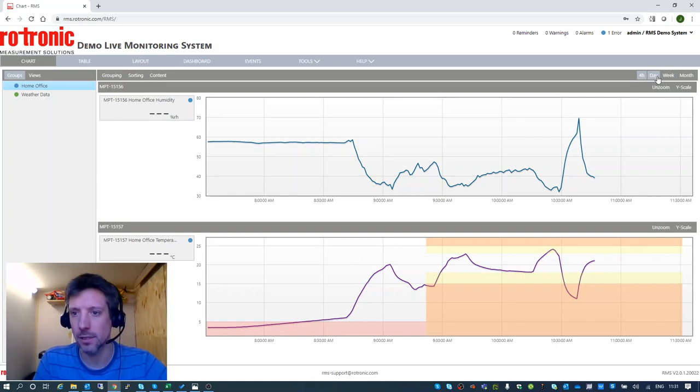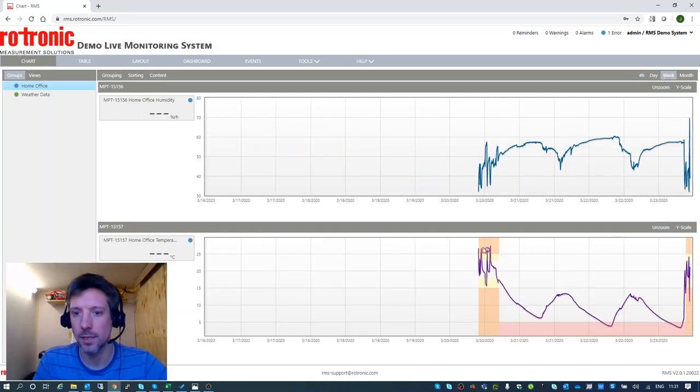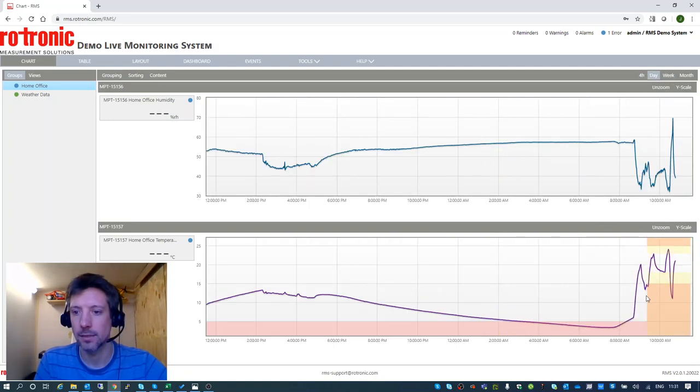But we can see that over the weekend we had, this was Friday's monitored data, and we can see the alarms adapting to that out of hours condition of just a 5 degree limit. We can see a few alarms over the cold winter nights or spring nights, and then on to today, logger coming in, heating on, a few spikes up and down, but the device is offline.